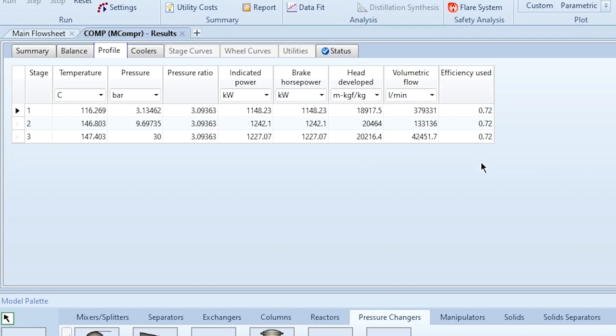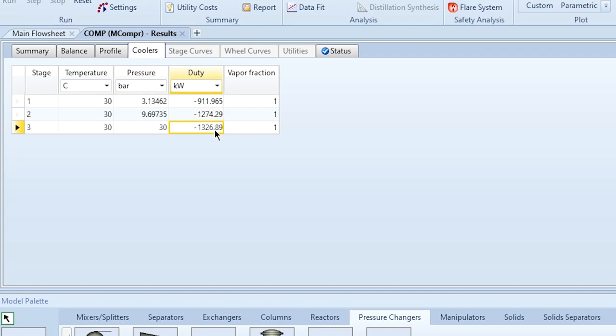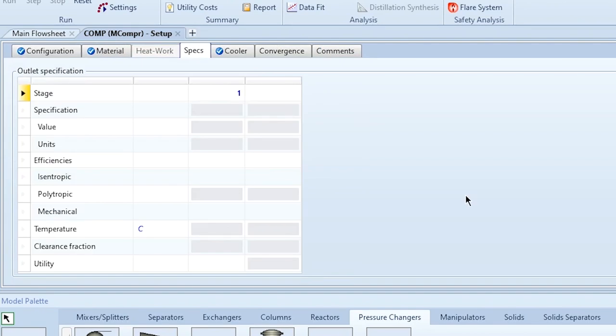The profile also shows head developed, volumetric flow rate, and efficiency. The default isentropic efficiency is 72%. You can also specify a custom efficiency value. In the Coolers section of the profile, heat duties are calculated for each compression stage — 911 kW for one stage, with values for the other stages calculated accordingly, giving a detailed analysis.